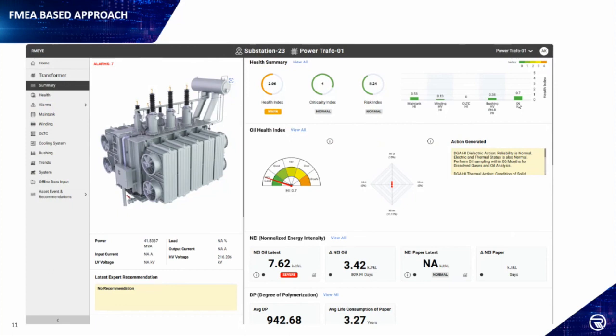Visual inspection is very simple: leakage. If leakage is observed from the main tank, the health score of the main tank goes higher. Higher means it's going toward the worst direction. Typically in this software, 0 means very good and 5 means very bad. So higher means it is going toward unhealthy or poor conditions.